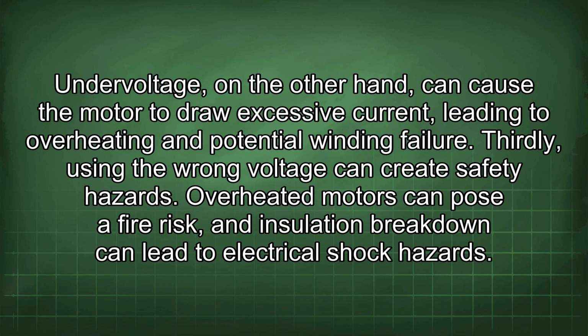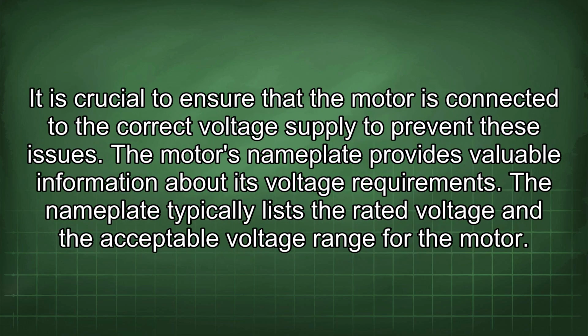Thirdly, using the wrong voltage can create safety hazards. Overheated motors can pose a fire risk, and insulation breakdown can lead to electrical shock hazards. It is crucial to ensure that the motor is connected to the correct voltage supply to prevent these issues.